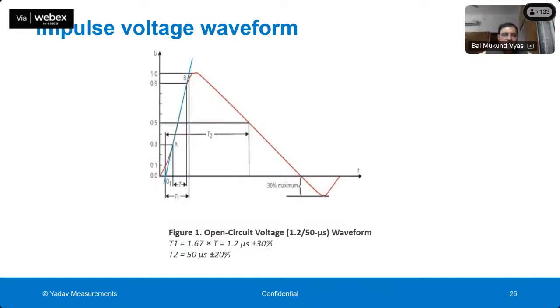This is the first test, for impulse voltage, and typically it is 6 kV of impulse which the meter has to face. This is a 6000 volt impulse waveform, which is shown here in red. It rises at a very fast rate and then it reduces. The typical rise time is 1.2 microsecond and the fall time is 50 microsecond. So this is the type of impulse the meter has to pass through.